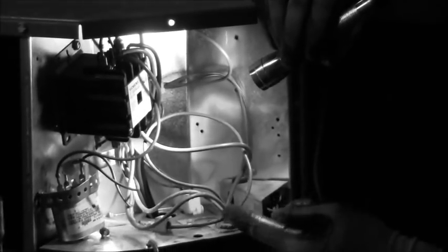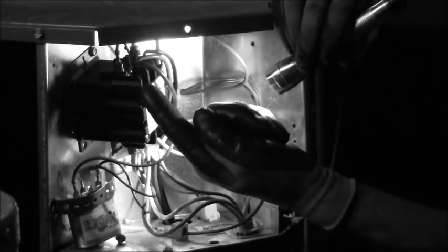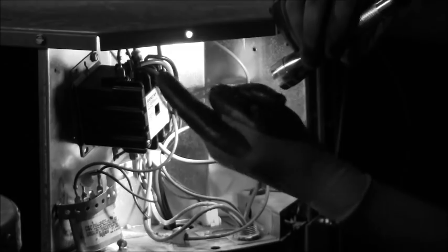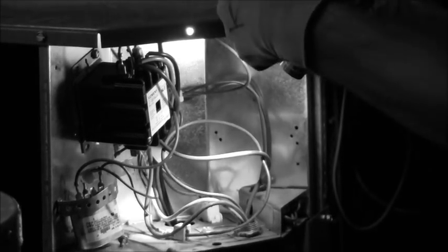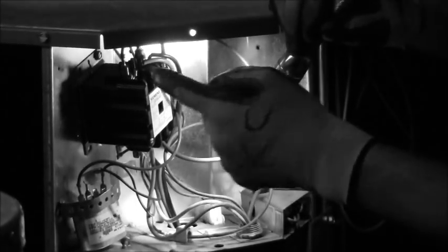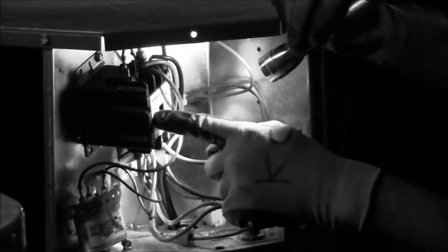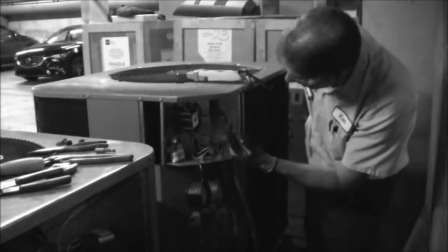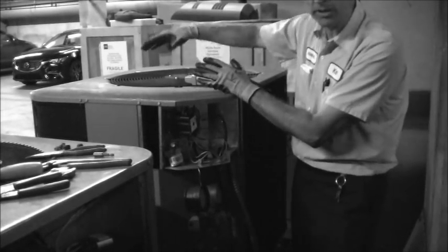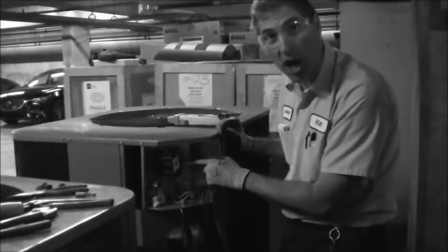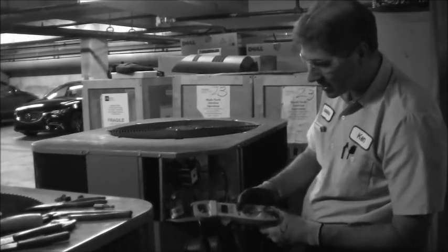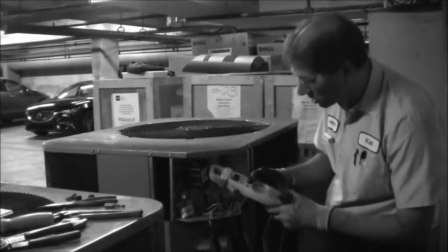So the electricity comes in through the bottom, it goes out through the top, it goes to the condenser fan motor, and the 3 phases go to the compressor. So that's how this whole thing works. But the contactor is pulled in, so I can get on either side of the contactor, but just so I'm on the side going closest to the motor and the condenser fan motor, I'll go on the top of this contactor. I'm going to do an NCV. Nothing is on the top.